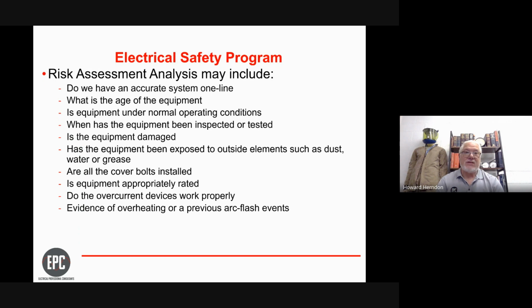One of the biggest impacts I see in the electrical industry is the use of impact guns. Everybody loves impact guns, but they can strip out covers, and if we do strip them out, we have to fix them. We can't just leave the bolt sitting there. Use a nut clip, a nut insert, rethread it to the next size, whatever the case might be. We need to make sure that we fix it.